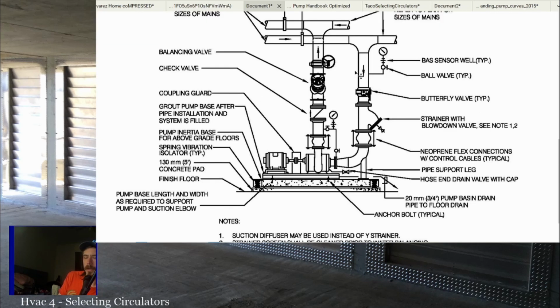On a circulator pump, the things that you generally want to have in the piping going to and away from the pump are a valve on the suction side, and that's just for service. It should never be closed at all, any amount, unless you're servicing the system. But if at all possible, having a valve before the pump is a good thing.